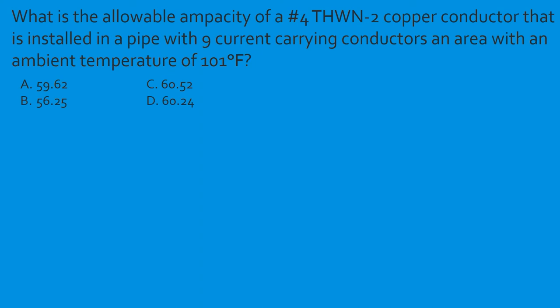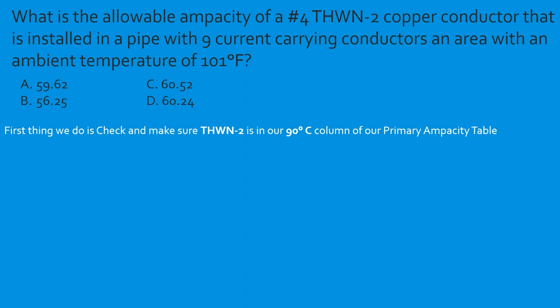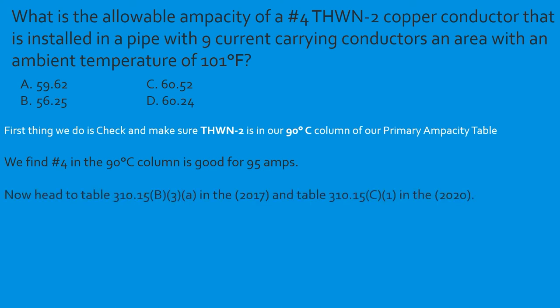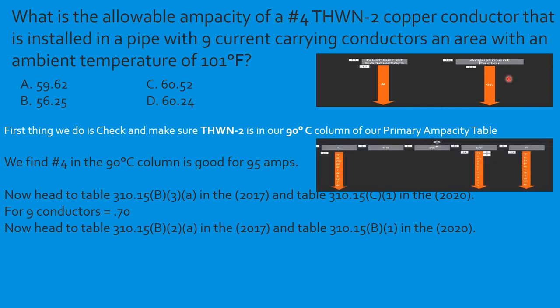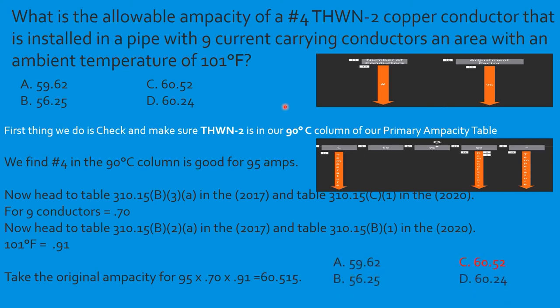Question: What is the allowable ampacity of a number 4 THWN-2 copper conductor installed in a pipe with nine current-carrying conductors in an area with an ambient temperature of 101°F? Confirm insulation is in the 90°C column. Number 4 copper is 95 amps. Nine conductors — bundling adjustment factor is 0.70. Temperature at 101°F — correction factor is 0.91. So: 95 × 0.70 × 0.91 = 60.515 amps. Select C.